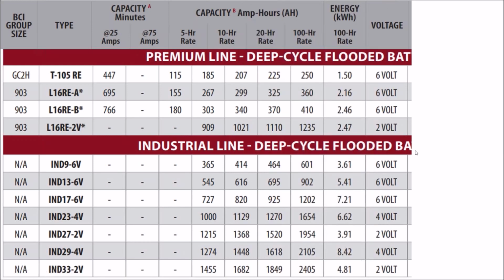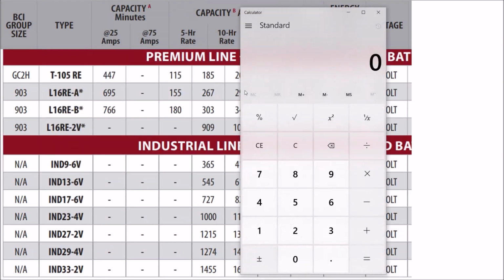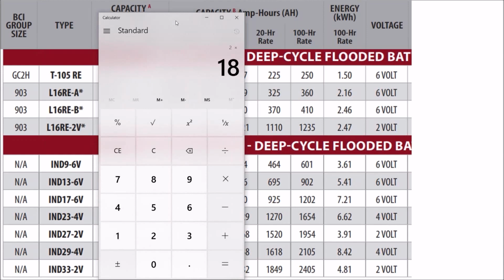What we're looking at here is a 2-volt battery, and the maximum 20-hour discharge rate is 1850 amps. So we have 2 volts times 1850 amps divided by 1000 — a volt times an amp is a watt — this battery is a 3.7 kilowatt hour battery if we're discharging it over a period of 20 hours.